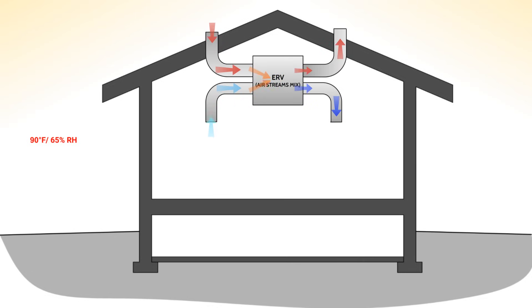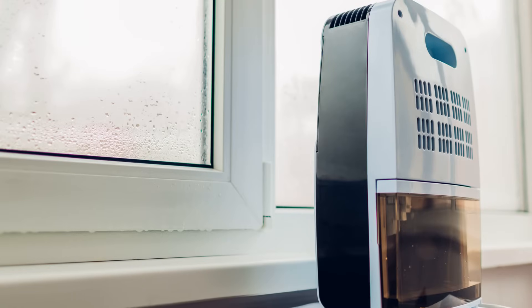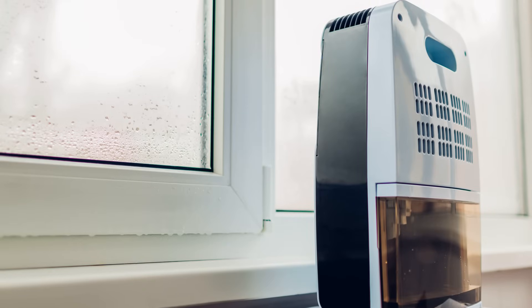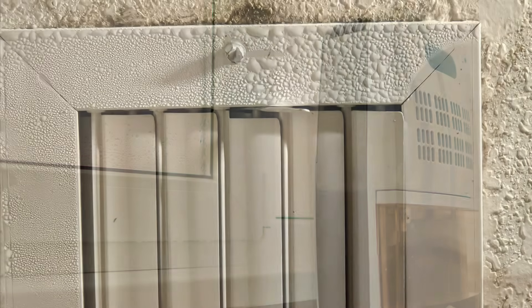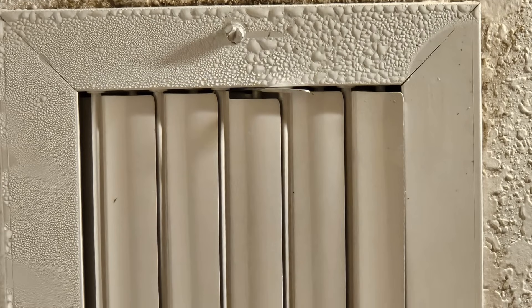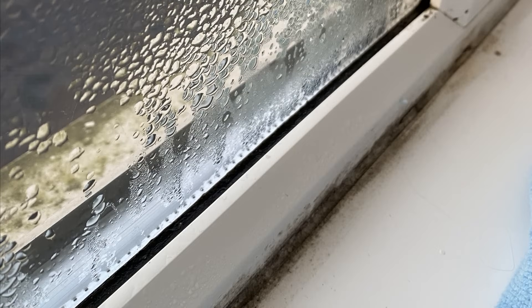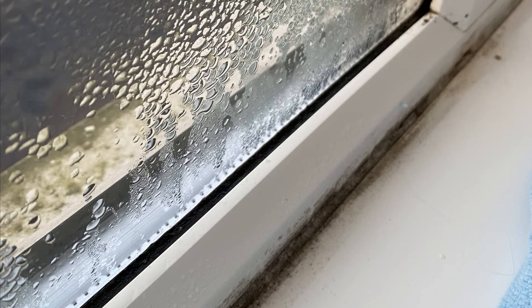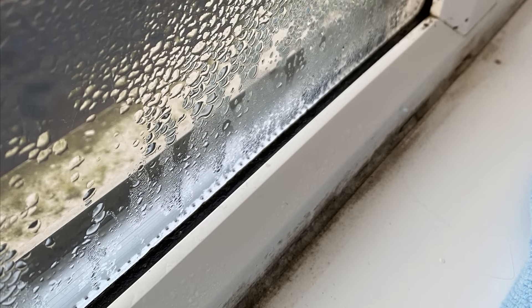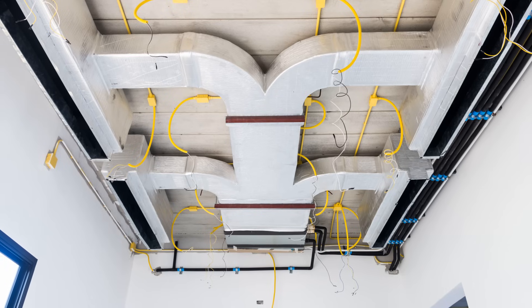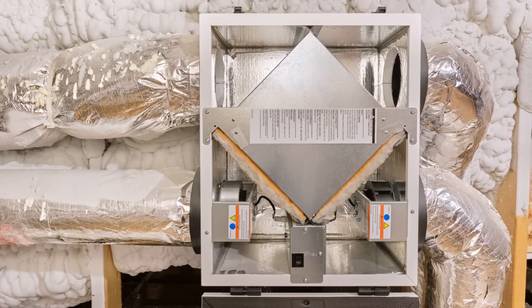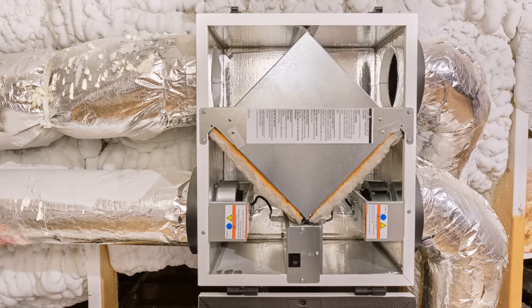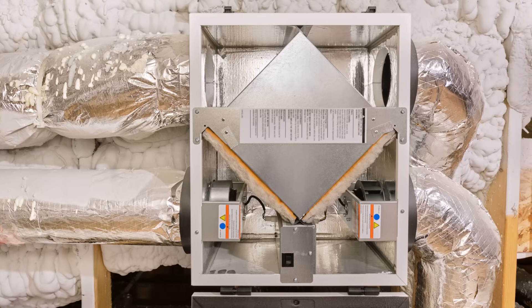But there's a tendency to overventilate, which not only can result in an energy penalty, but it can result in humidity issues, since during the warmer months the air that's being brought in tends to be more humid than the conditioned air inside. So we have to make sure that we're ventilating at an appropriate rate relative to the needs of the occupants to keep interior relative humidity at a safe level.